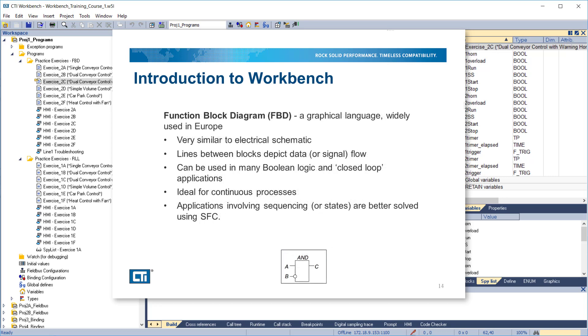Structured text is considered the base language of Workbench. Function block diagram is a graphical language which is widely used in Europe. It's very similar to an electrical schematic. Lines between blocks depict data or signal flow. It can be used in many Boolean logic and closed-loop applications, and is ideal for continuous processes. Applications involving sequencing or states are better solved using SFC.